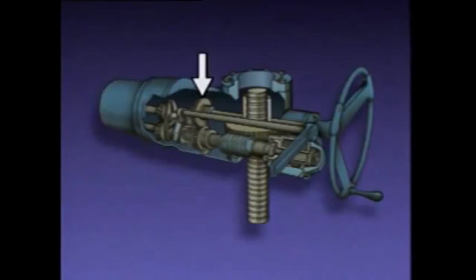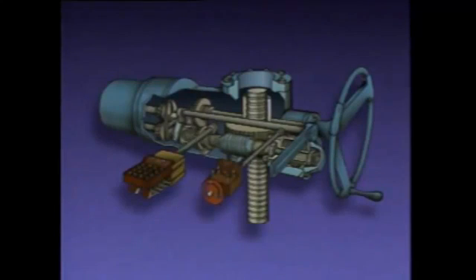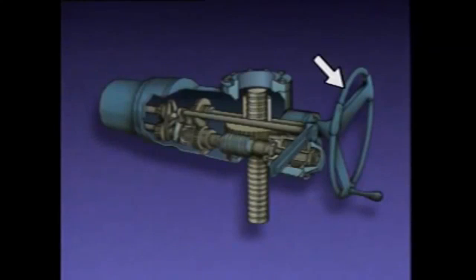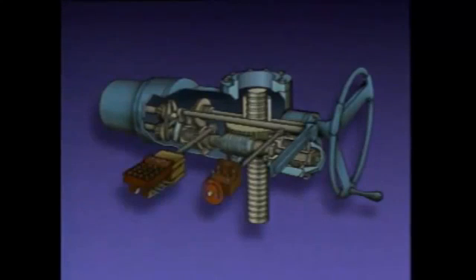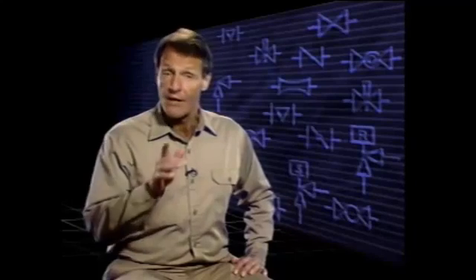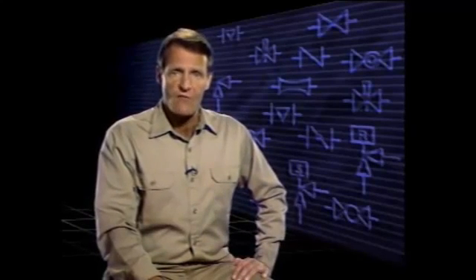The limit switch and torque switch in the motor operator ensure that the valve is positioned without damaging the valve or the motor operator. The torque switch deals with the torque — the amount of turning force produced by the motor operator. It cuts off current to the motor when the torque reaches a preset amount, limiting force on the valve stem to prevent damage while ensuring a tight seal between the valve disc and seat.